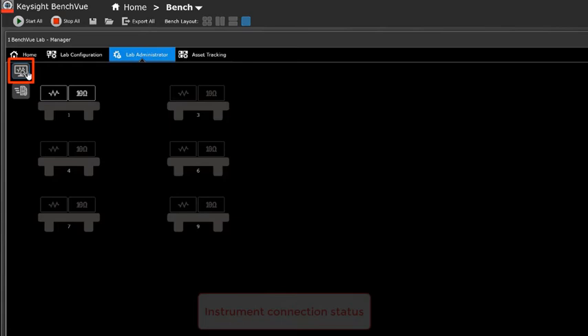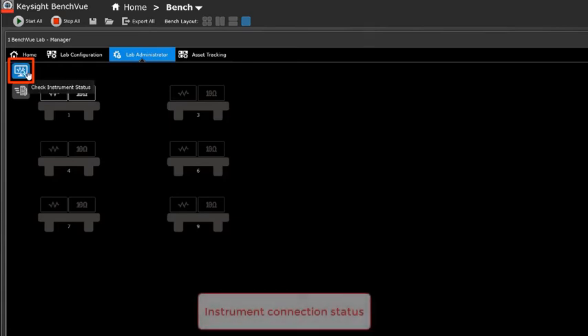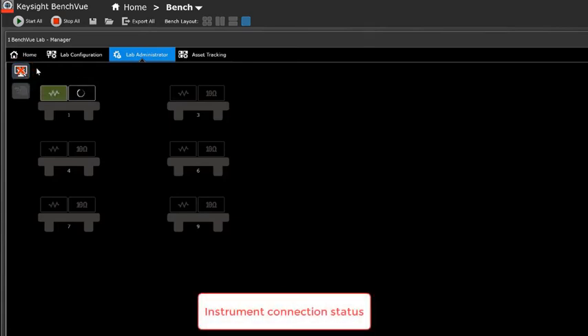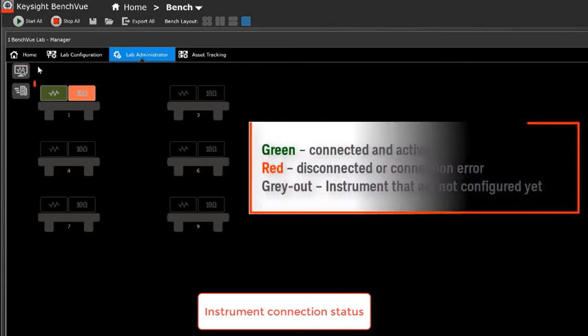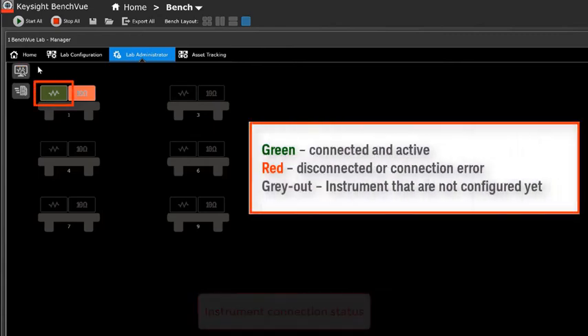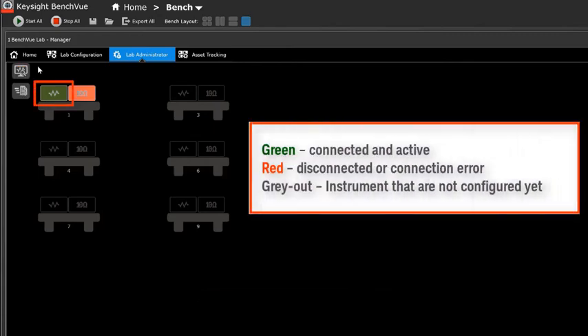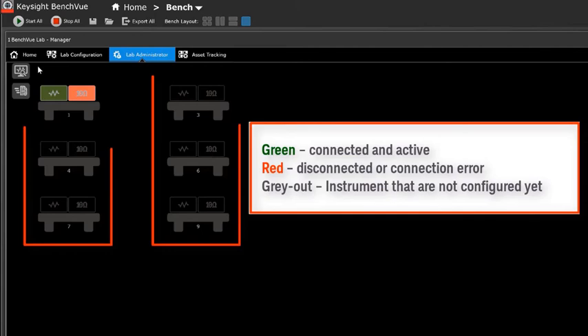Click on the check instrument status icon to check all the instrument status. The color code of green indicates the instrument is connected and active, red indicates disconnected or connection error, and the gray out shows the instrument is not configured yet.